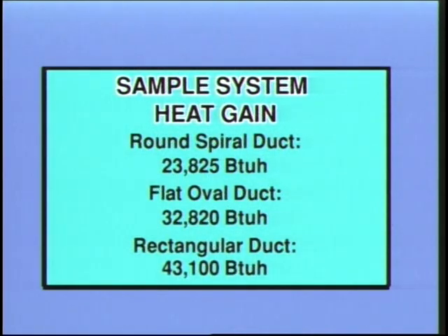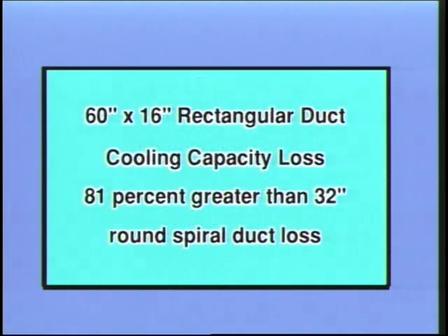And the 60-inch by 16-inch rectangular duct heat gain under similar conditions was calculated at 43,100 BTU per hour, or an 81% greater loss of cooling capacity than that with the round spiral duct system under the same thermal conditions. If space was too limited to use the 32-inch round spiral duct, the use of smaller, multiple round spiral ducts with the same airflow requirements could be used. However, multiple ducts would have a higher cooling capacity loss through the attic than that with a single round duct.